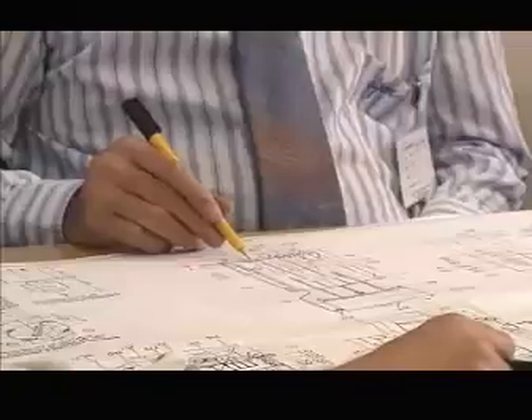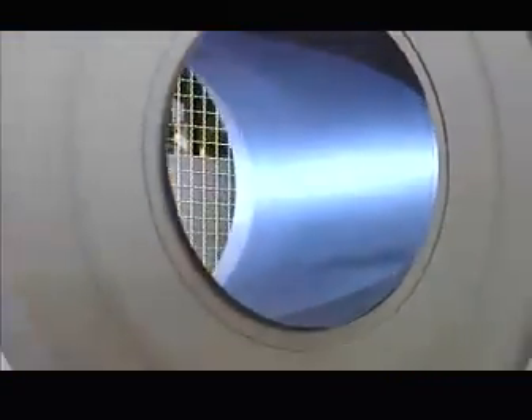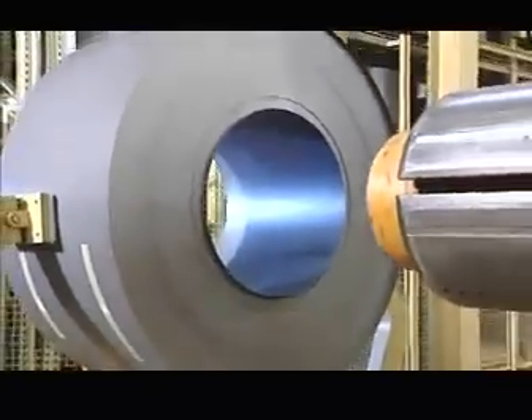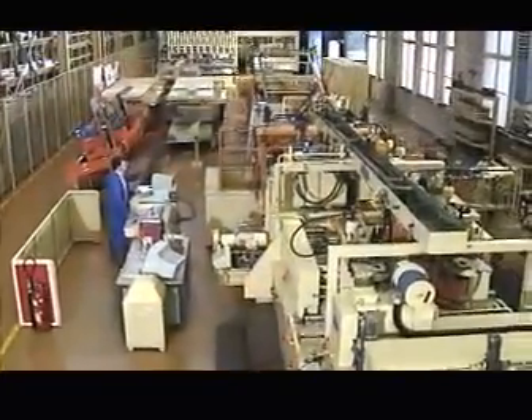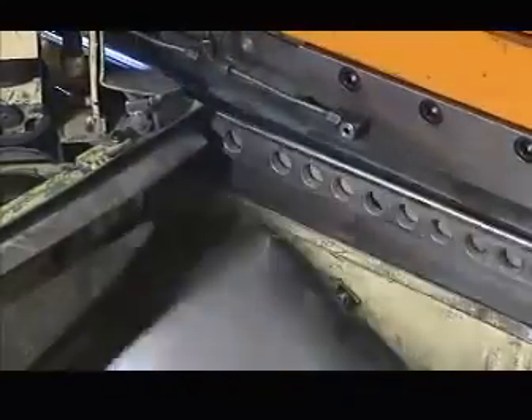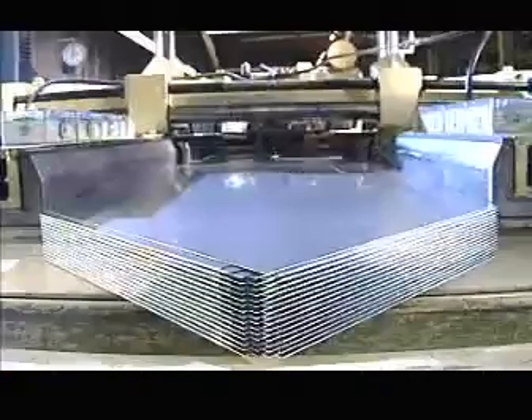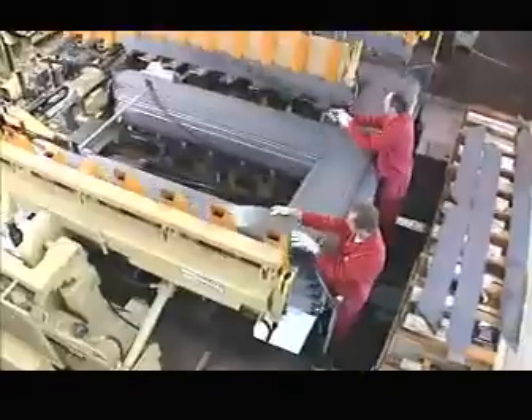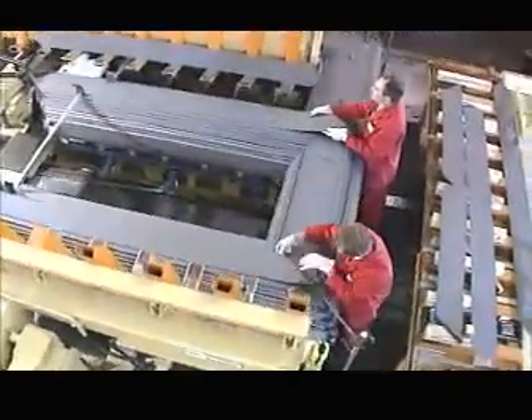Production. Coils are wound on the cores. Depending on the customer's requirements for loss and noise levels, we use high B laminations or laser and plasma treated laminations. Laminations up to 6 meters long are built up into cores on special staggering benches. The step-lap staggering method offers the optimum solution in terms of low noise and electrical losses.